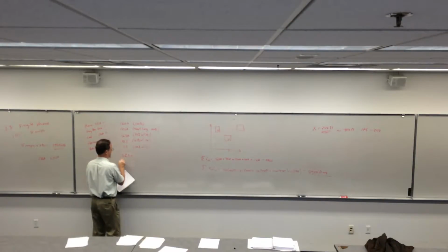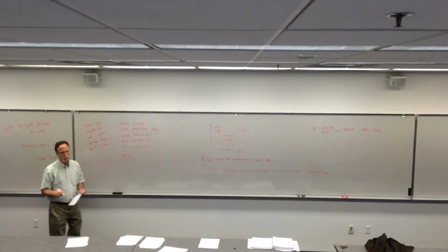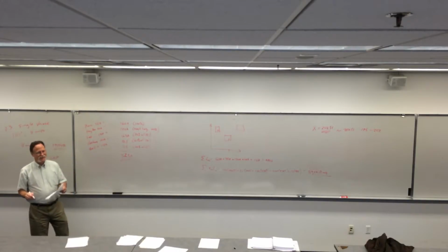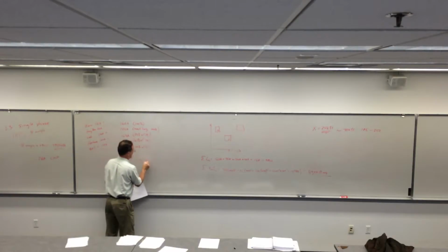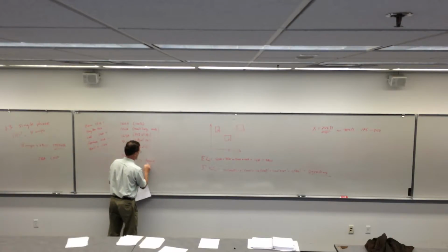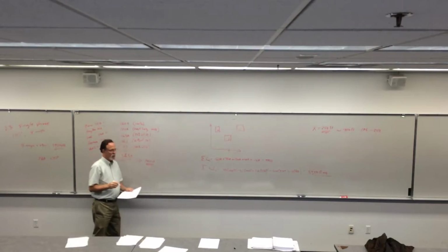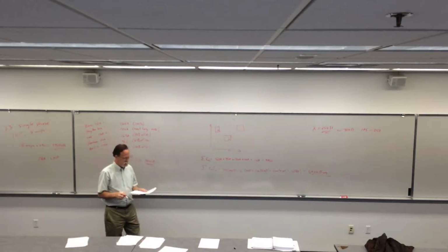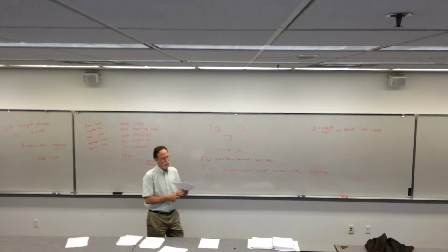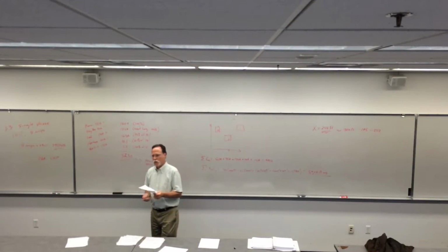So I add all this stuff up, and I get 376.3 amps. So what do I get for my service? 376, so 400. I put in a 400 amp service if I want a little bit of overage. Actually, I have to go to the next size up. That's a requirement. Now, you have to watch the well business. You want the well separate.